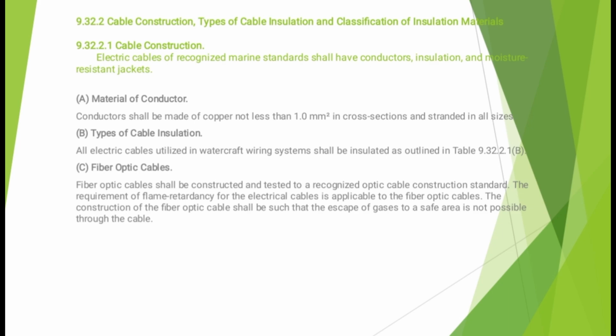C. Fiber optic cables. Fiber optic cables shall be constructed and tested to a recognized optic cable construction standard. The requirements of flame retardancy for the electrical cables are applicable to the fiber optic cables. The construction of the fiber optic cable shall be such that the escape of gases to a safe area is not possible through the cable. So, conductors must utilize copper with a minimum cross-sectional area of 1.0 mm² to ensure adequate current carrying capacity, and they shall be stranded for flexibility and durability.